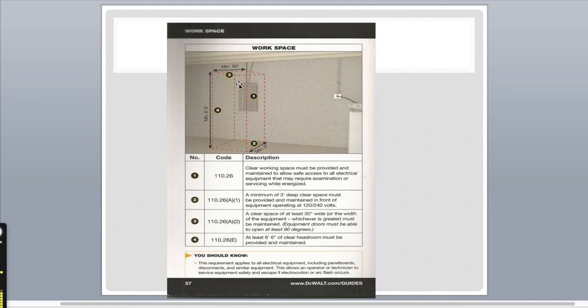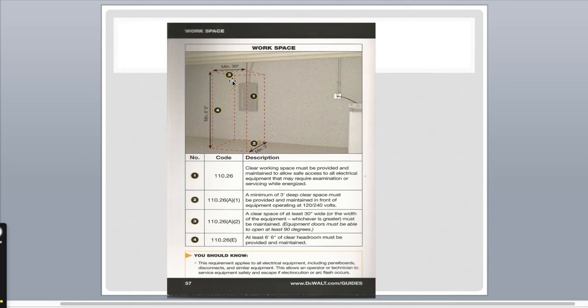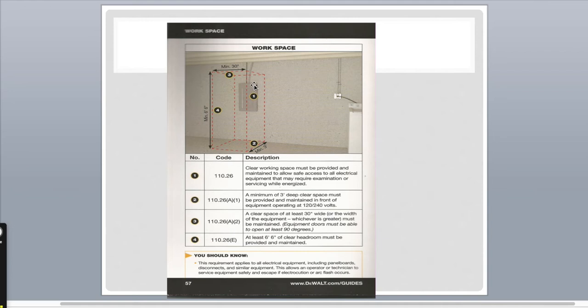Right here it shows you 30 inches above and 3 feet front to back and 6.5 feet up. So they want that much clearance around this service. And that is to protect whoever's working on that panel so they don't get stuck on it if anything unfortunate happens.